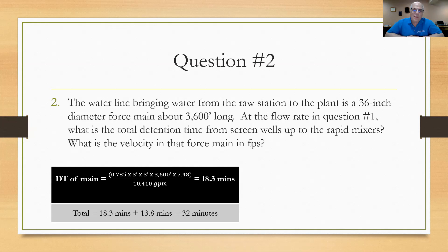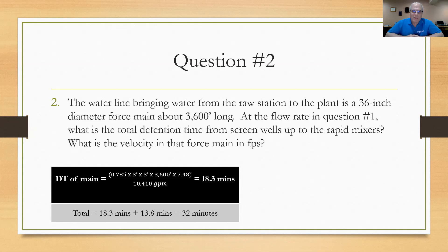The reason operators need to know that total detention time is because when adding permanganate, at the typical pH levels, they need 20 to 25 minutes of reaction time for the permanganate to work. To avoid pink water arriving at the water plant, you need to confirm sufficient detention time along the way. This calculation proves there is enough time for the permanganate to react.